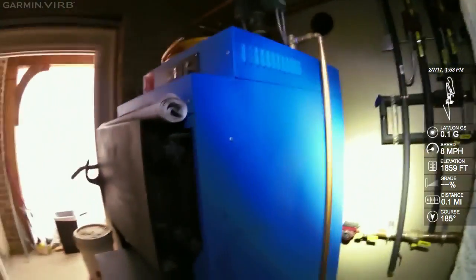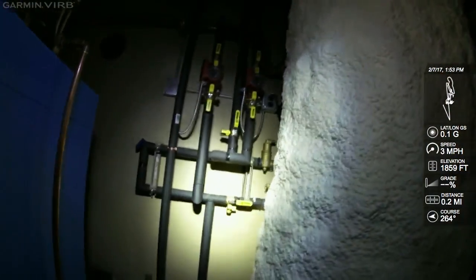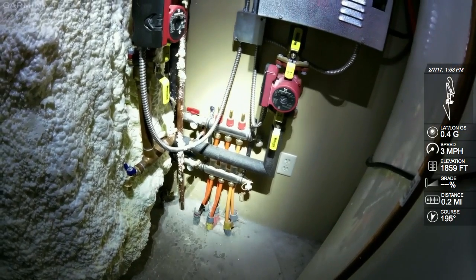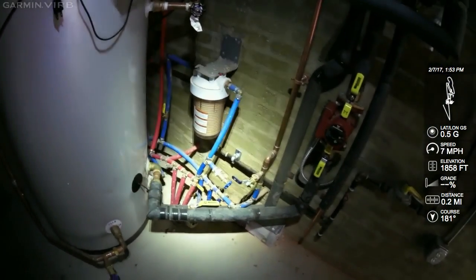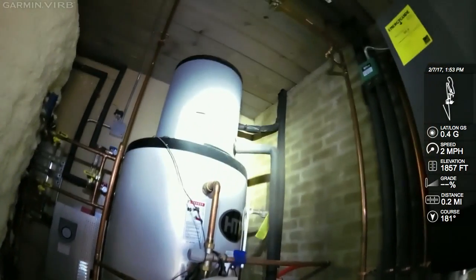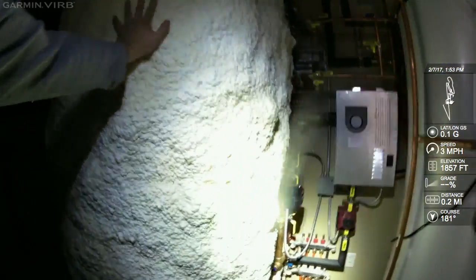This guy's done most of this out-of-pocket, which is crazy to me. This is an awesome heating system — he's got a gasification boiler. The gasification boiler heats this buffer tank, and then the buffer tank pushes water into the slab, so they're heating this house with radiant. He's got a couple more zones, and he's also got a solar hot water system — drain back. There's the drain back tank and the solar storage tank.